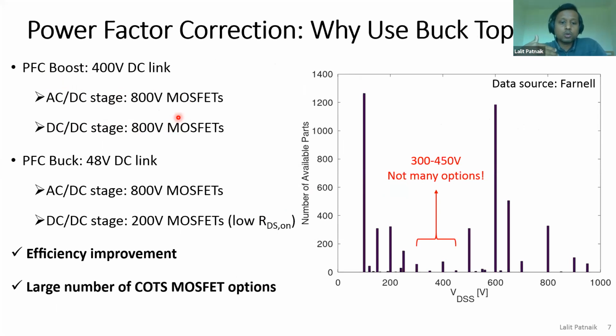The point is, because we are using this power supply in radiation-exposed applications, you need to derate the VDS rating of the MOSFET. So if the maximum blocking voltage expected in this topology is around 375 volts, a 400 volt or 500 volt MOSFET isn't enough—you have to use double the required voltage. So 800 volt becomes the standard value, which you have to do anyway for the AC-DC stage. But if the DC-DC input is 400 volts, even the DC-DC stage will have to use such high voltage rated MOSFETs.